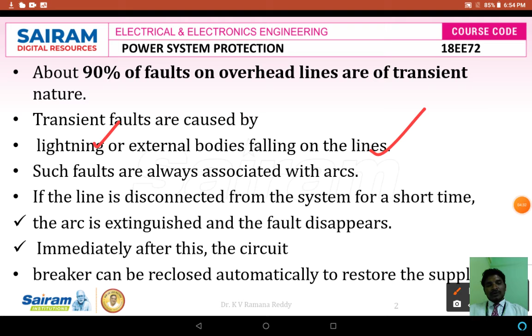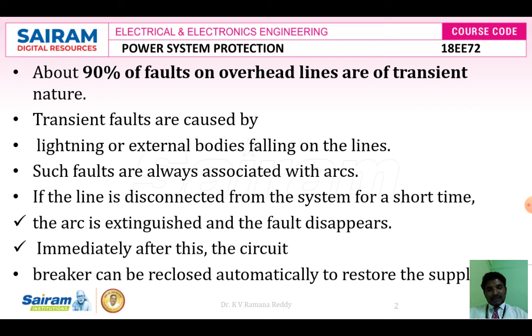Most of the faults on extra high voltage lines are caused by lightning, and during that interval, flashovers take place across insulators due to overvoltages caused by lightning, and these lightning overvoltages may exist just for a short time. Hence, an instantaneous recloser is used in the case of extra high voltage lines. So instantaneous reclosure is used in extra high voltage lines after clearing the fault, either an overvoltage fault or an overcurrent fault. Immediately the circuit breaker switch has to reclose, and again it has to restore the supply voltage, and there is a need to increase the stability of the system, because the circuit breaker is activated only at the time of the fault. The rest of the time the circuit breaker switch remains closed, and it has to transfer the current and provide continuity of electrical power supply.